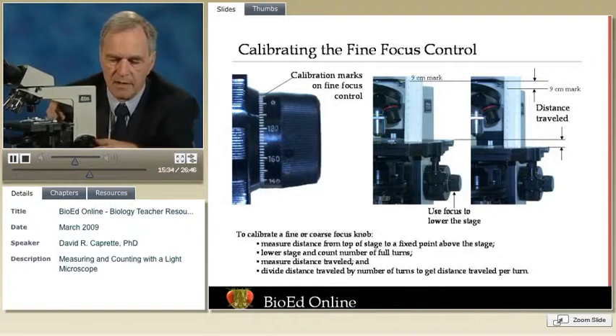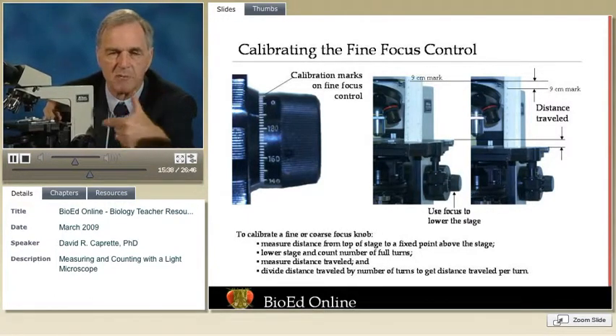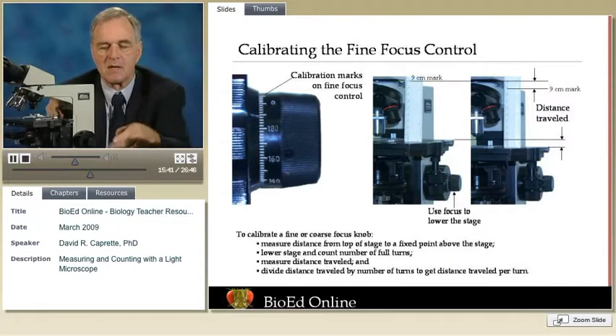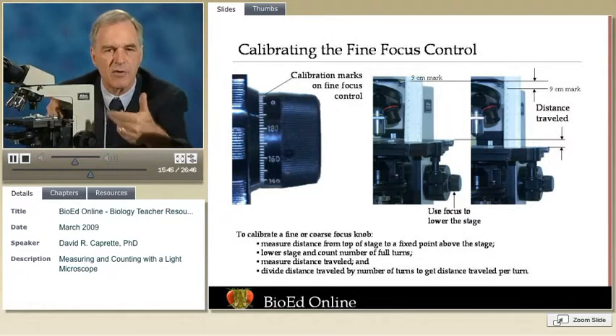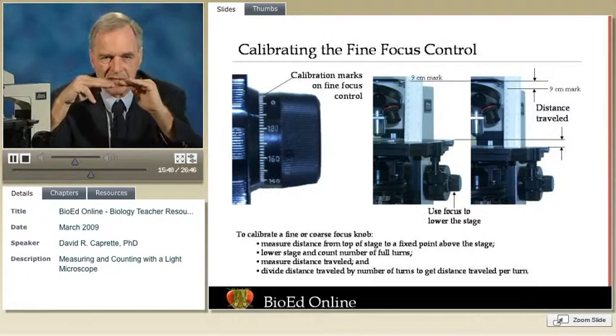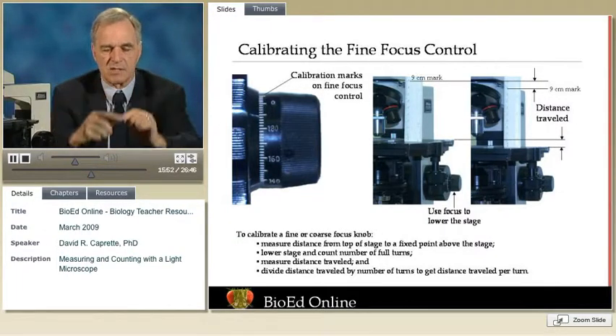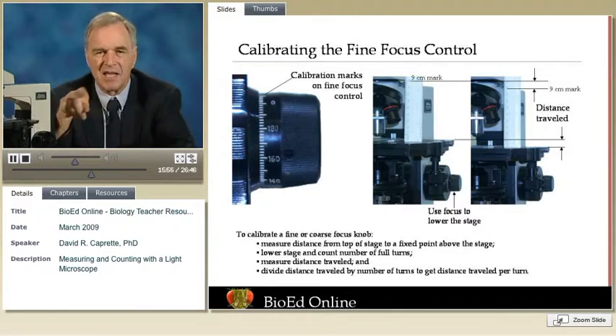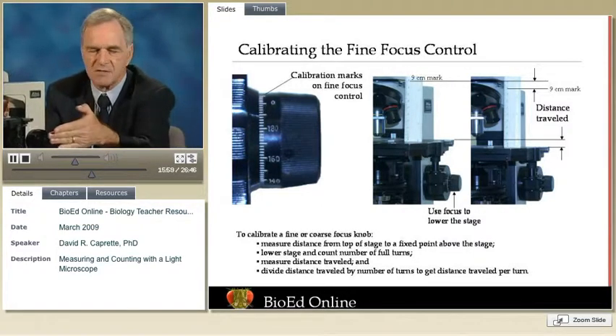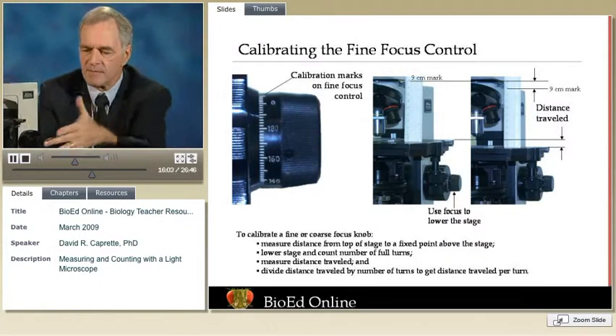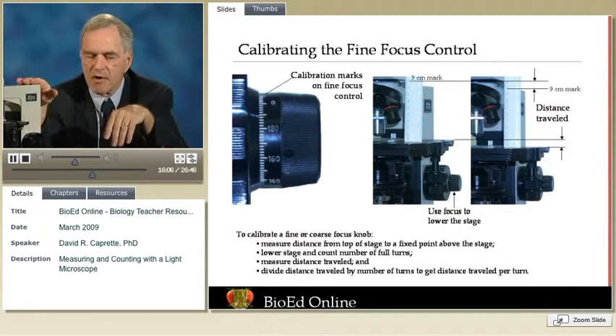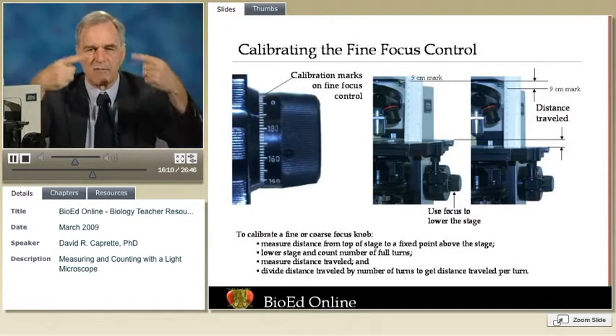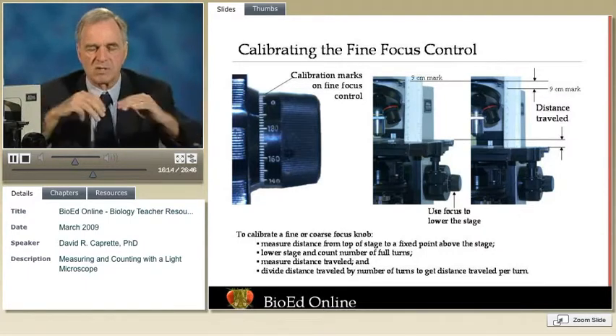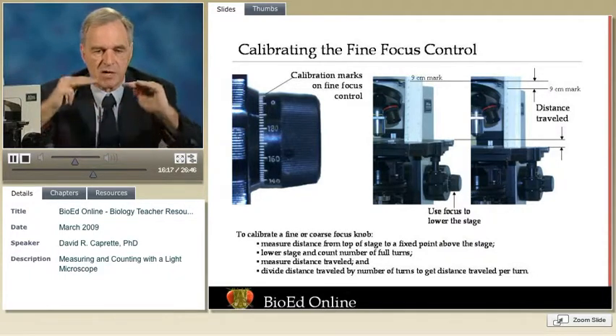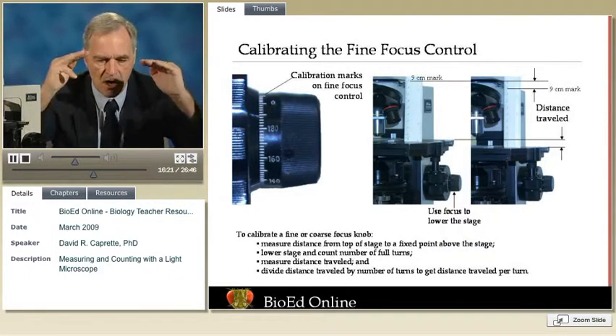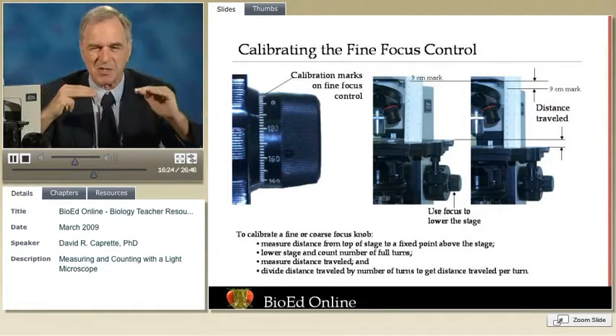If you move the fine focus in one direction and you stop at a particular point and you note the focus, and then you go past that point and come back, rotate it in the other direction and come back to the same point, you should be in the same place. Chances are you won't be. Hysteresis is the principle by which the direction of change influences the final result. And with these fine movements, no matter how well engineered the focus rack is, hysteresis can make it very difficult to get very accurate measurements, particularly if you're moving in different directions, moving the stage up, moving the stage down. One thing I would recommend, if you're going to do a series of measurements this way, is to always start either below the specimen or always start above it and measure in the same direction each and every time.